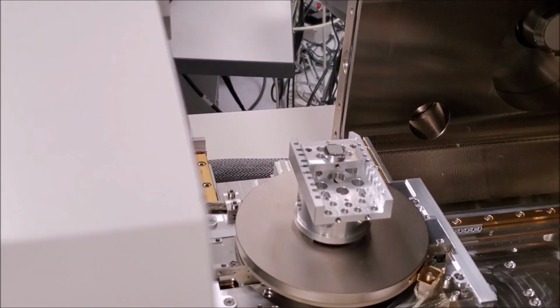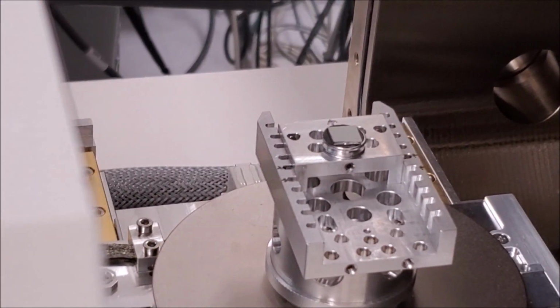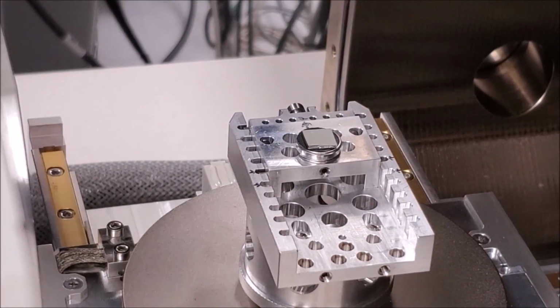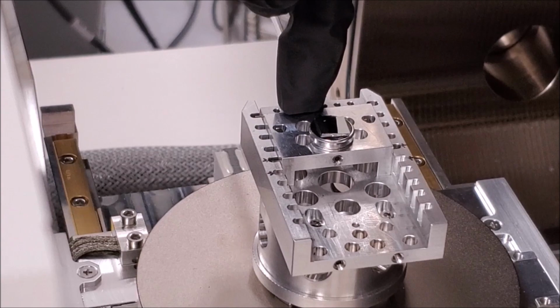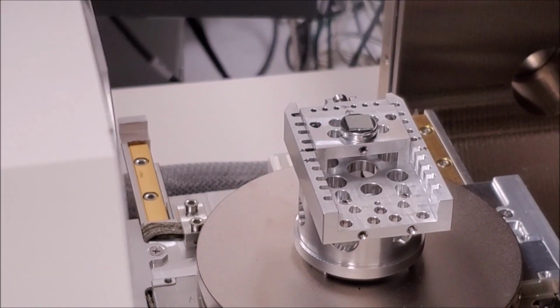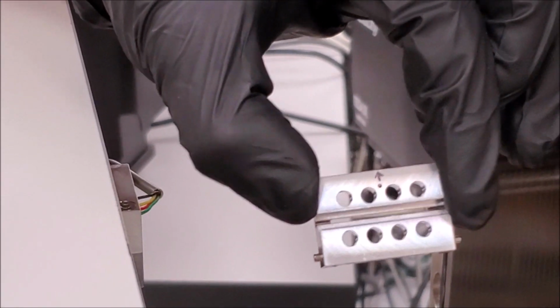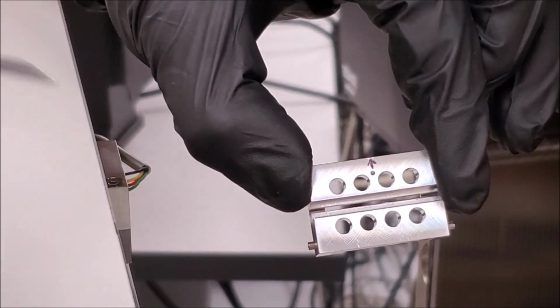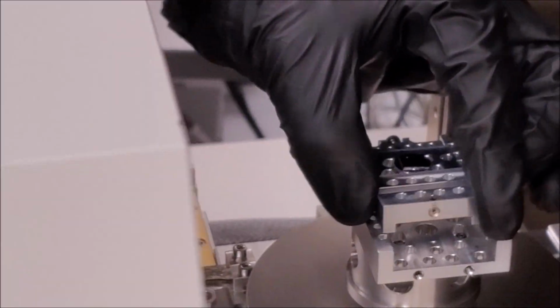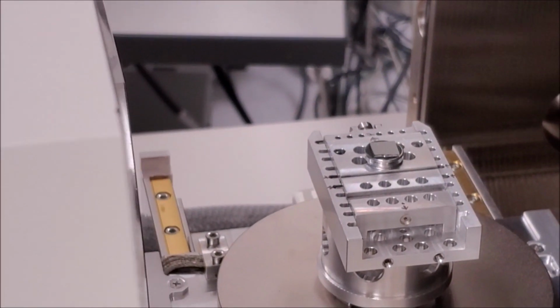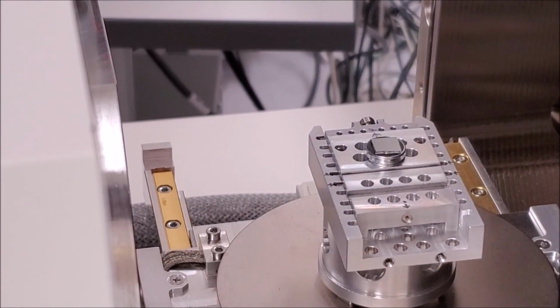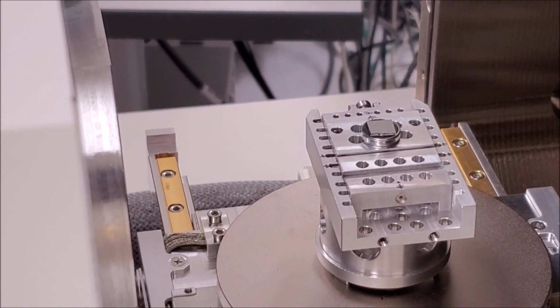Then load a clamping bar onto the universal mounting base on the other side of the module, making sure that it is properly oriented with the correct side up. Then gently hold it down and then tighten down the screw on the clamping bar. The grid holder module can be loaded similarly into the universal mounting base. However, the grid holder needs to be placed into the module first before tightening down the clamping bar.